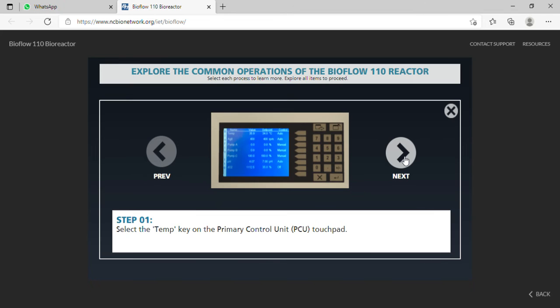Step 1. Select the temperature key on the primary control unit PCU touchpad. Step 2. Select the setpoint on the PCU. This will take you to the setpoint menu. Step 3. Enter 35 degrees Celsius on the PCU touchpad. Step 4. Select Enter to accept the new value. Step 5. Select Return to go back to the PCU main menu. Step 6. You have now completed the setpoint activity.